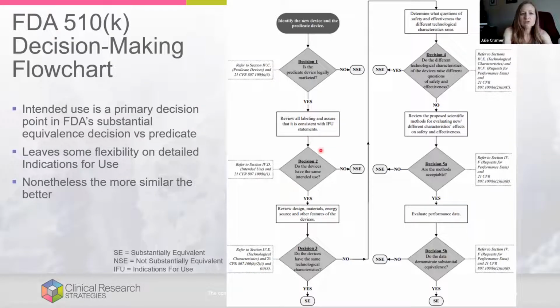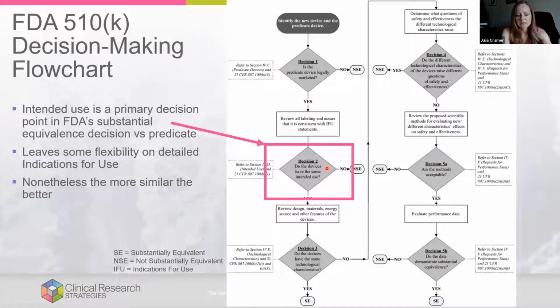So decision 2 is, do the devices have the same intended use? So I will say here that the intended use is the primary decision factor that the FDA uses to determine substantial equivalence of a predicate device, but the more similar, the better. So again, that intended use was the more broad term. The intended use of our insulin pen was injecting insulin to increase insulin levels in the bloodstream. And the indications for use was that specific condition, disease, diabetes. And so the more similar you are, the better there, but intended use has got to be the same. If yes, then you're going to review the design, the materials, the energy source, and all the features of the devices, compare the two of them.